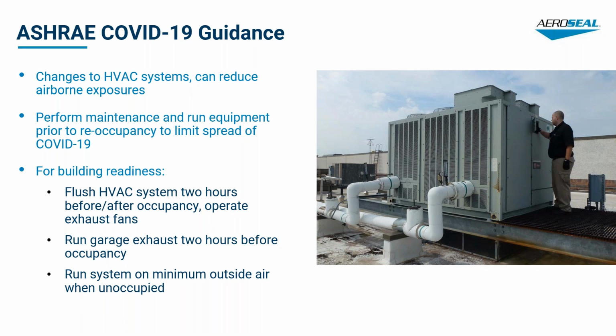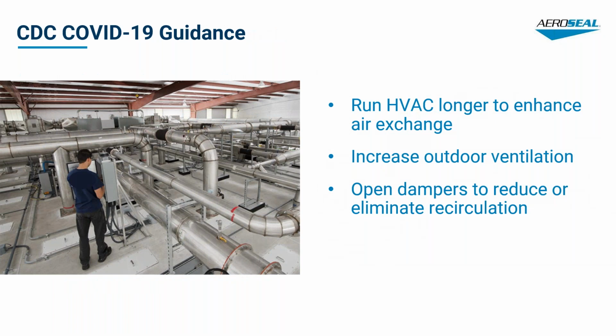ASHRAE has some guidance on this. They're saying changes to HVAC systems can reduce airborne exposure, so people are really admitting this is an issue. ASHRAE is telling us to flush the HVAC system, operate exhaust fans more, and run the system on minimum outside air even when the building is unoccupied. The CDC says you want to run the HVAC longer to enhance air exchange, increase outdoor ventilation, and open dampers to reduce or completely eliminate recirculation.